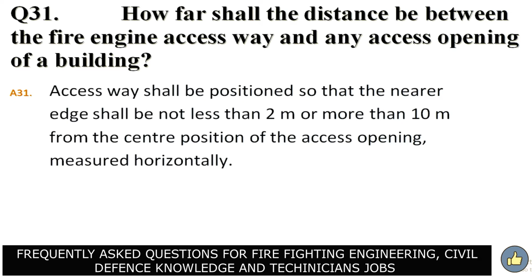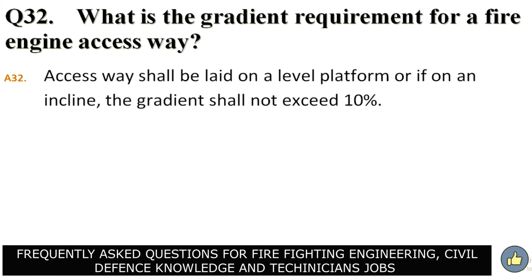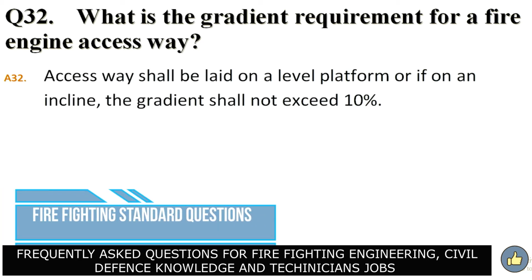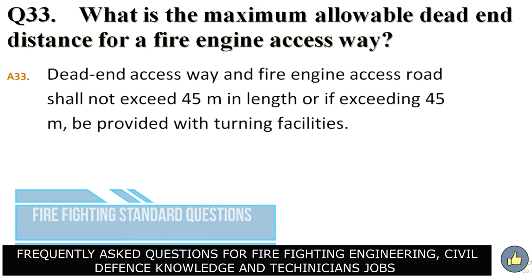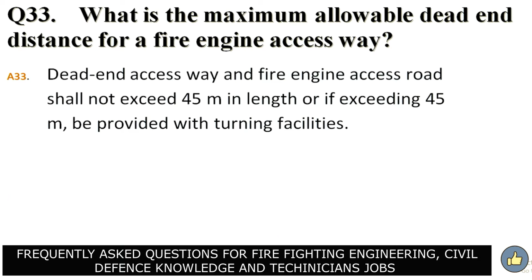building? Answer. Access way shall be positioned so that the nearer edge shall not be less than 2 meters or more than 10 meters from the center position of the access opening measured horizontally. What is the gradient requirement for a fire engine access way? Answer. Access way shall be laid on a level platform, or if on an incline, the gradient shall not exceed 10%. What is the maximum allowable dead end distance for a fire engine access way? Answer. Dead end access way and fire engine access road shall not exceed 45 meter in length, or if exceeding 45 meter, be provided with turning facilities.